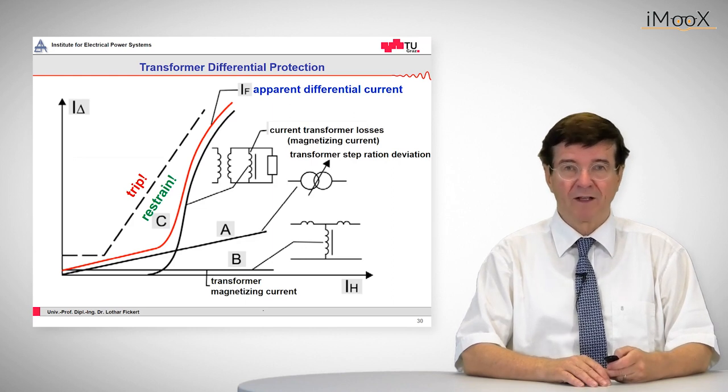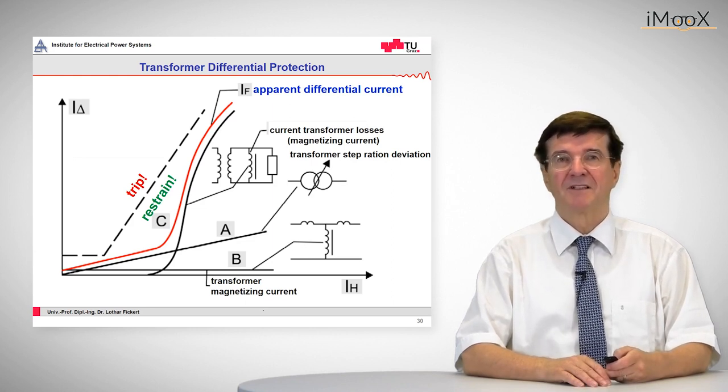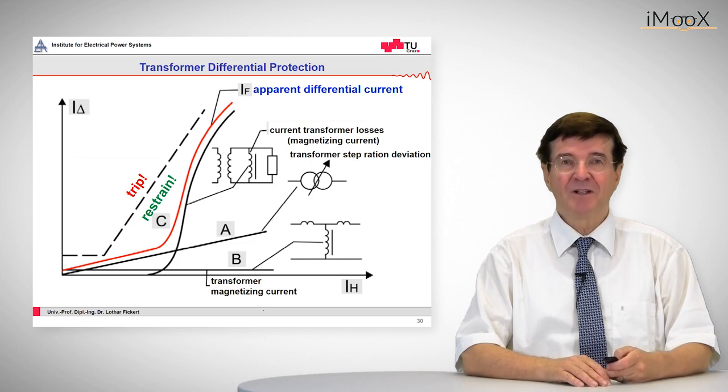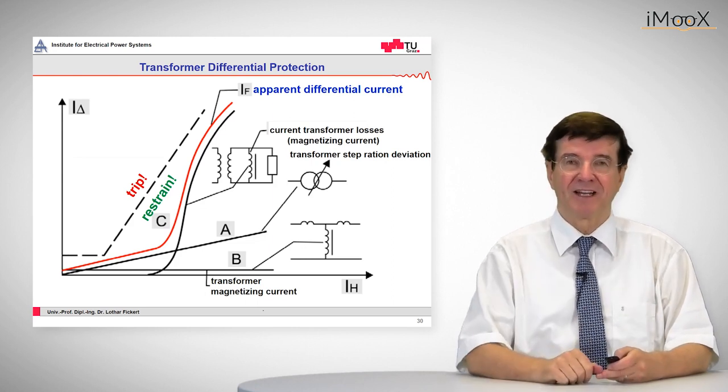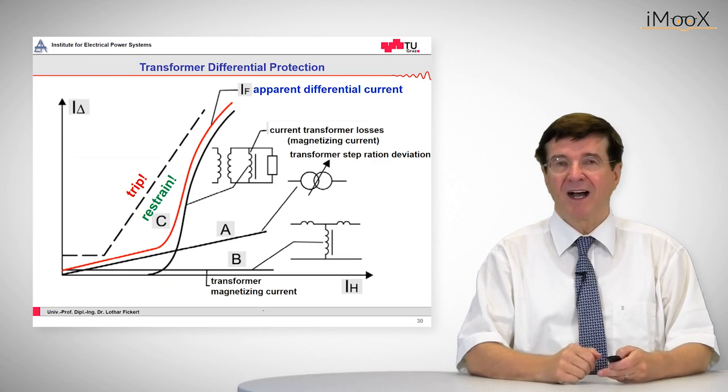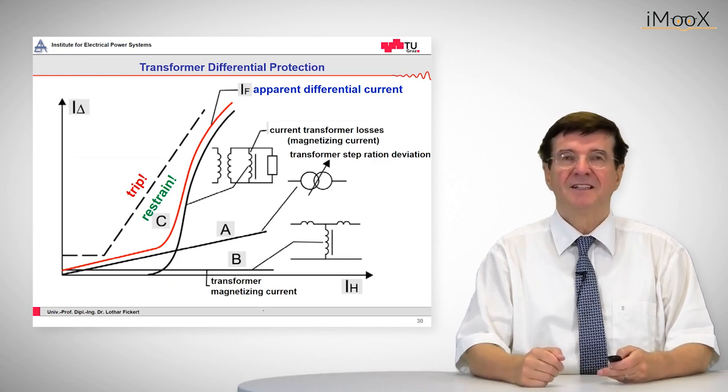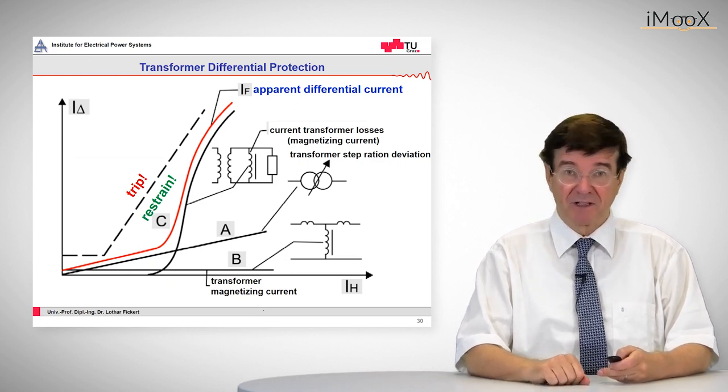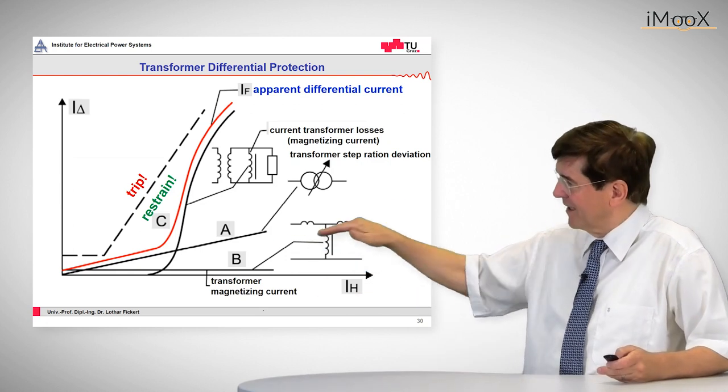For example, one is if we have a tap changing transformer where the ratio between the primary and the secondary side varies. Then the higher the through current is, the bigger is the apparent differential current. So this is a straight line that goes up.